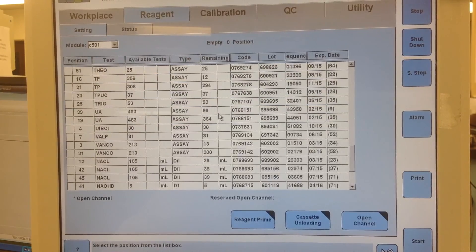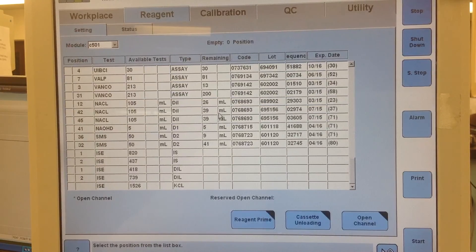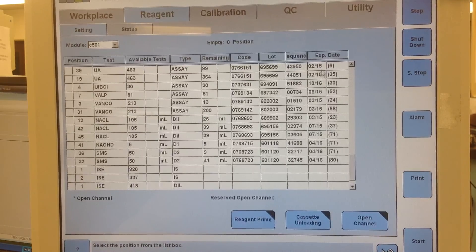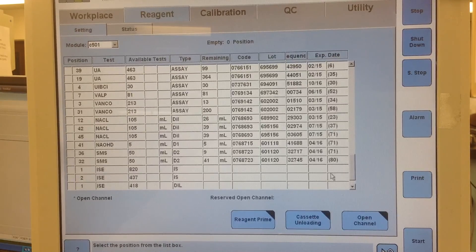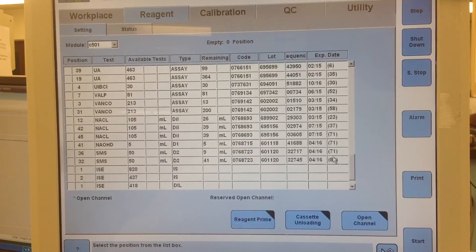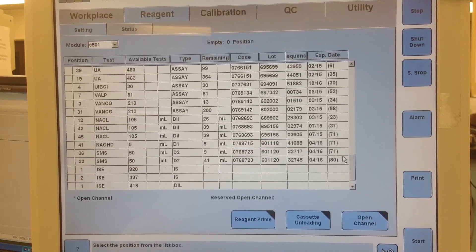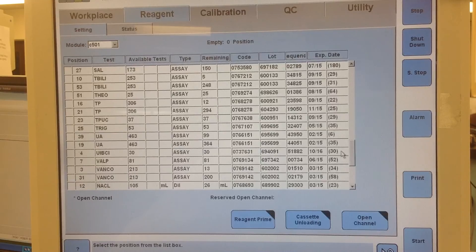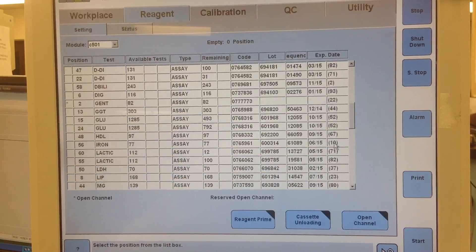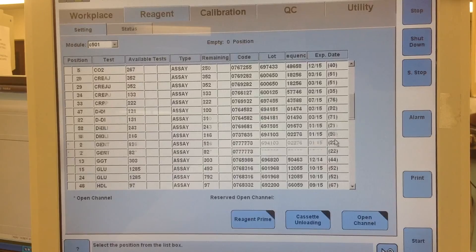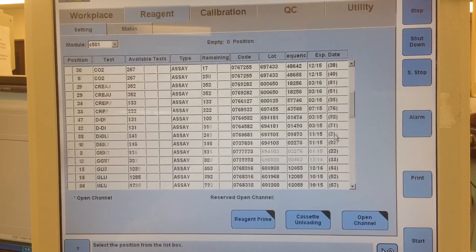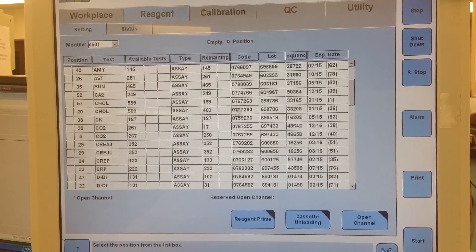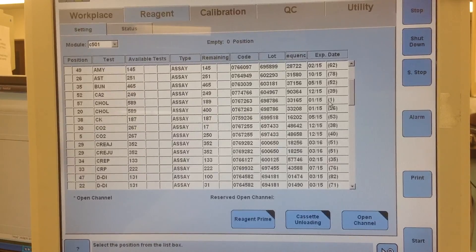After that I'll scroll down and check all that, and the next thing I want to do is come over here to the expiration date and check for any of the reagent packs that have either already expired last night at midnight or will expire tonight at midnight. So you just quickly scroll through. It shows you all the days it has left until it expires. For instance, direct bilirubin only has two days left, so cholesterol only has one day left.